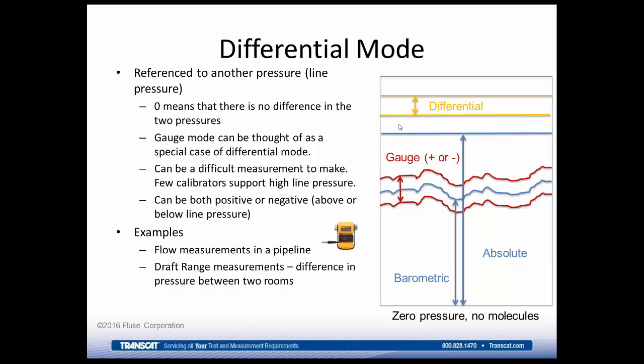To determine the flow of the fluid through that pipeline, you may put an orifice in place. As the fluid flows through that orifice, it'll create a pressure differential across the orifice, where the pressure on one side is higher than the pressure on the other side. If you know what that pressure difference is, then you would be able to calculate the flow of the fluid. That pressure drop is much lower than the overall line pressure. So if the line pressure is a couple of thousand psi, that pressure drop will most likely be lower than, say, 30 psi. So it can make the overall measurement pretty difficult.